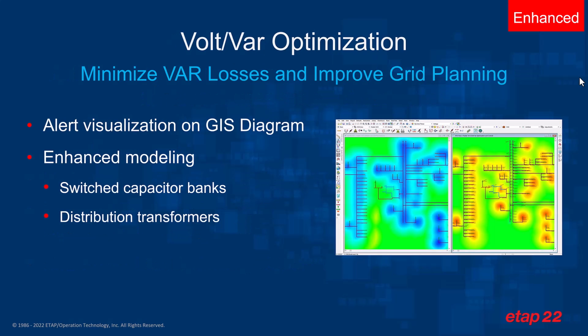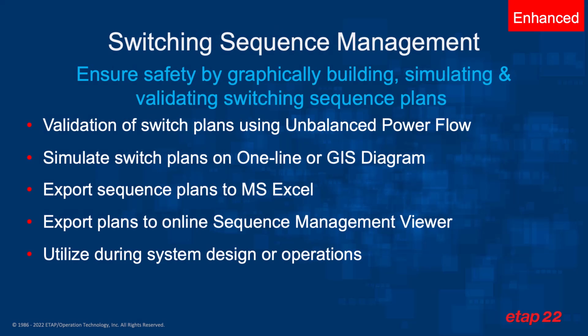Volt var optimization allows utility planners to minimize reactive power losses and of course improve overall grid planning through the use of edge devices for voltage and var support. This module has been enhanced to include alert visualization directly on the GIS diagram, and we've also enhanced the modeling of switched capacitor banks as well as distribution transformer tap changers. Switching sequence management allows the users to ensure safety by graphically building, simulating, and validating the switching sequence plans.